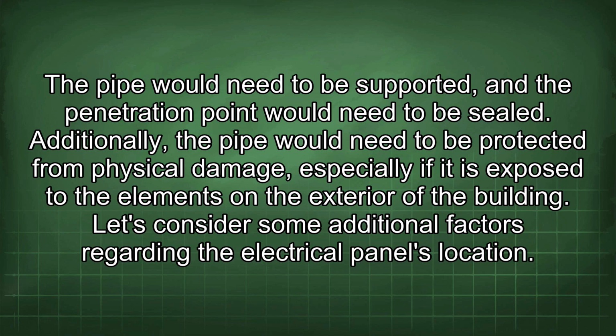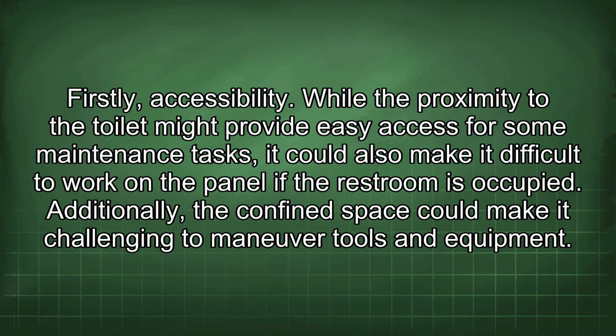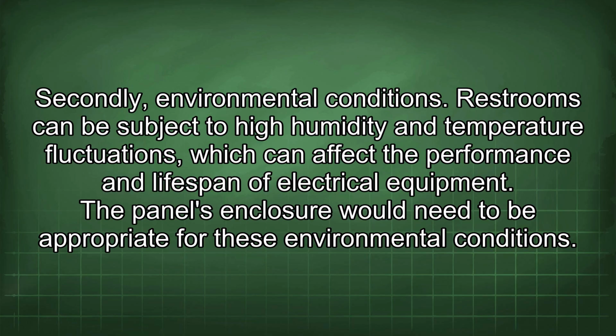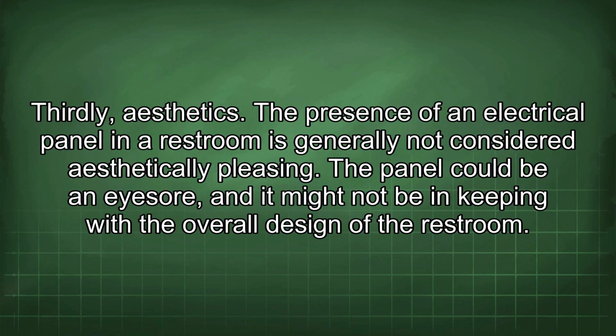Let's consider some additional factors regarding the electrical panel's location. Firstly, accessibility. While the proximity to the toilet might provide easy access for some maintenance tasks, it could also make it difficult to work on the panel if the restroom is occupied. Additionally, the confined space could make it challenging to maneuver tools and equipment. Secondly, environmental conditions. Restrooms can be subject to high humidity and temperature fluctuations, which can affect the performance and lifespan of electrical equipment. The panel's enclosure would need to be appropriate for these environmental conditions. Thirdly, aesthetics. The presence of an electrical panel in a restroom is generally not considered aesthetically pleasing. The panel could be an eyesore, and it might not be in keeping with the overall design of the restroom.